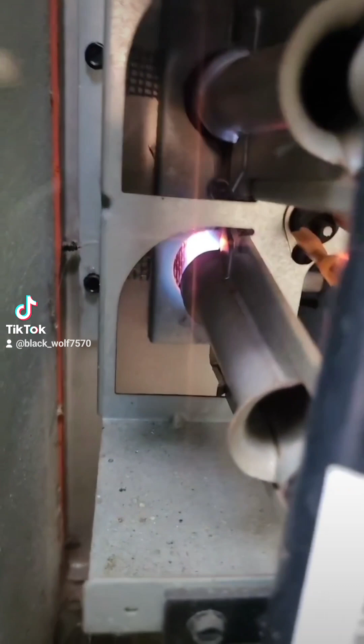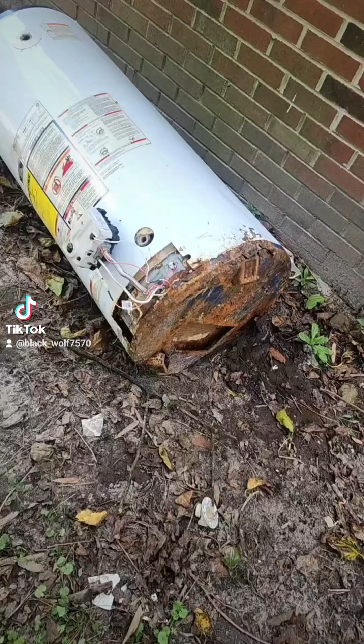Notice how that bottom jet started, and a few seconds later the top jet started. That burner jet right there is pretty much just coated with rust, which prevents the flame from migrating up. And after a while, it actually just cooked it out, and then it fired off on its own. So during maintenance, we take those out, clean the burner jets, and make sure it will pass the flame clearly. I used to drive past these all the time, think no mind of it, and now I see money. Yoink that, don't mind if I do.